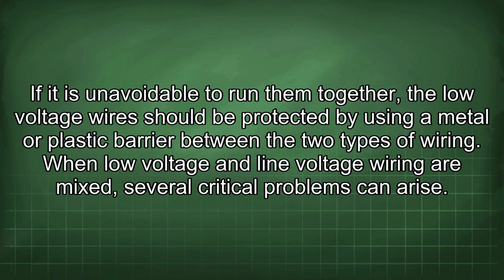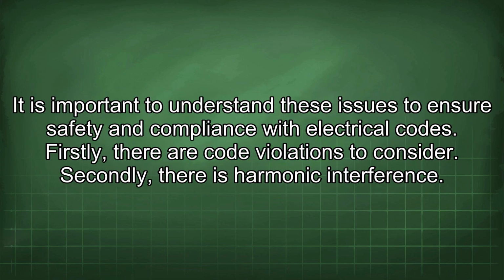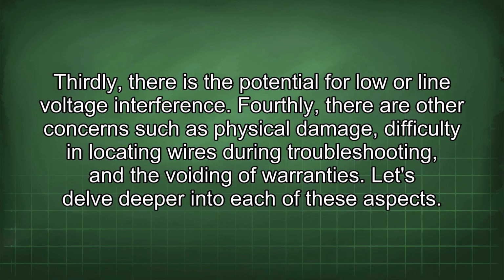When low voltage and line voltage wiring are mixed, several critical problems can arise. It is important to understand these issues to ensure safety and compliance with electrical codes. Firstly, there are code violations to consider. Secondly, there is harmonic interference. Thirdly, there is the potential for low or line voltage interference. Fourthly, there are other concerns such as physical damage, difficulty in locating wires during troubleshooting, and the voiding of warranties. Let's delve deeper into each of these aspects.